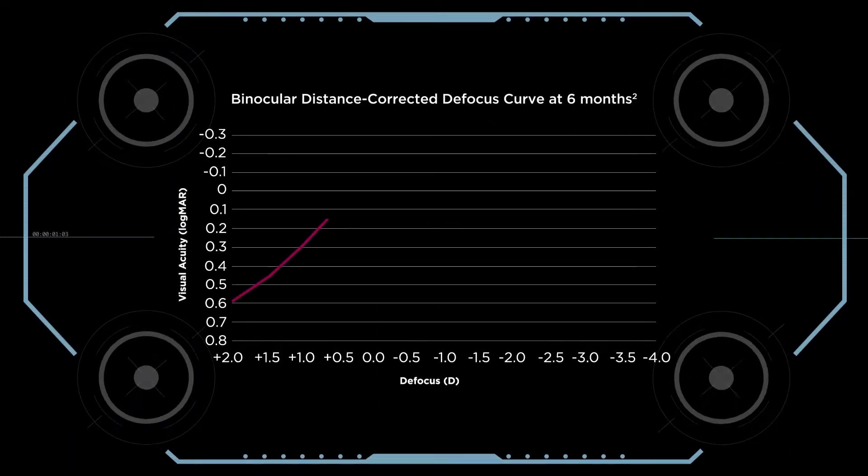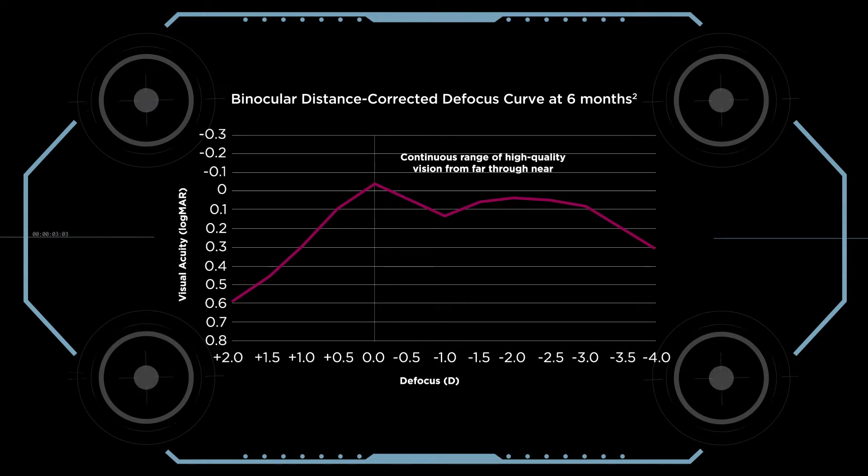The profile of the 15 diffractive rings of the Technis Synergy IOL create constructive and destructive interference to optimize light distribution. This modification of the diffractive profile and base curve alter the phases of light. This results in a lens that delivers continuous vision from distance through 33 cm.